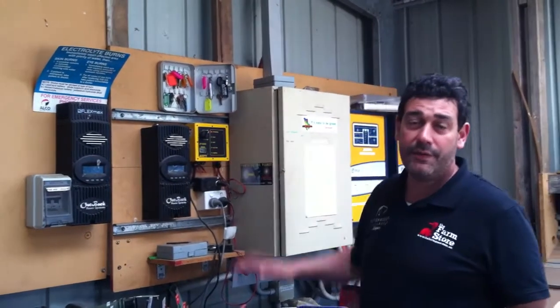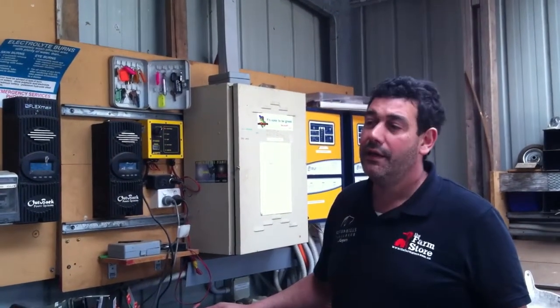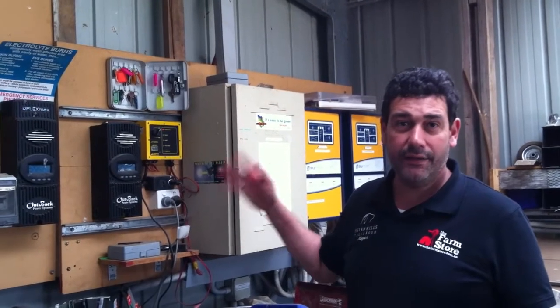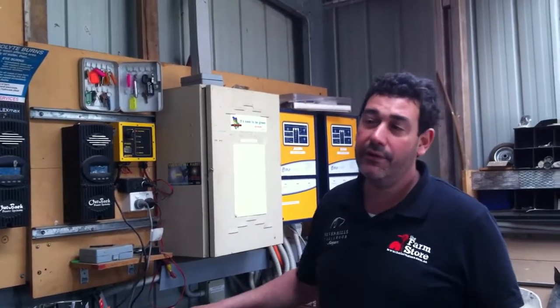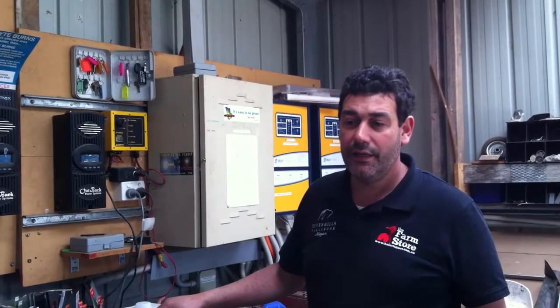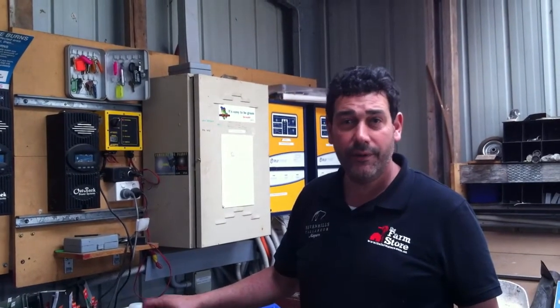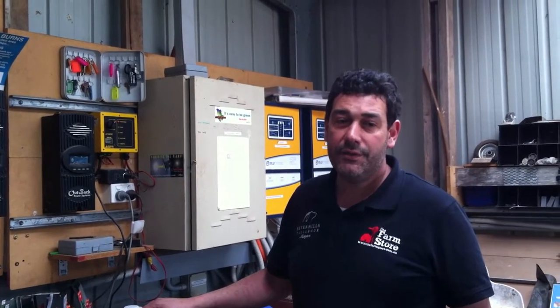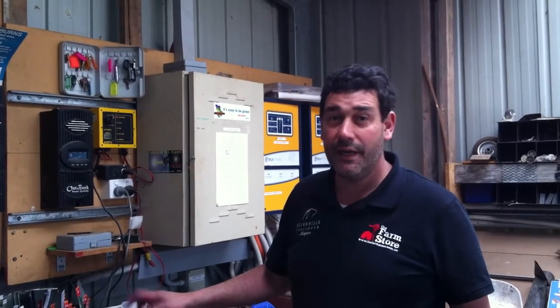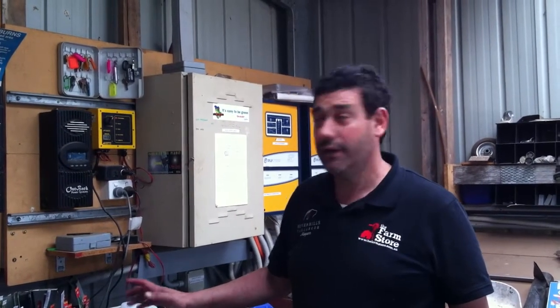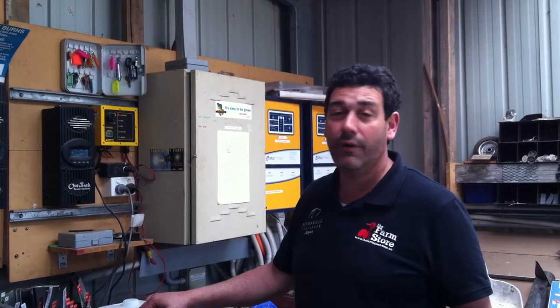If the pulse isn't long enough, sometimes it fails and won't start. It'll try once or twice to restart and then shut down and go into alarm mode. When it goes into alarm mode, it's hooked up to a security company. As soon as the alarm's registered, they give me a call to say we've lost power here, and we can come in and have a look to see what's gone wrong.